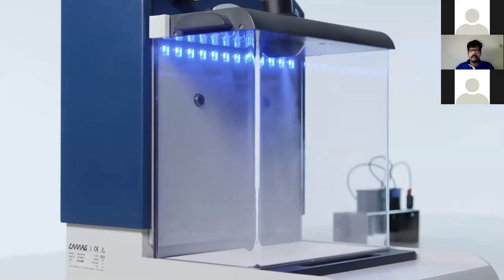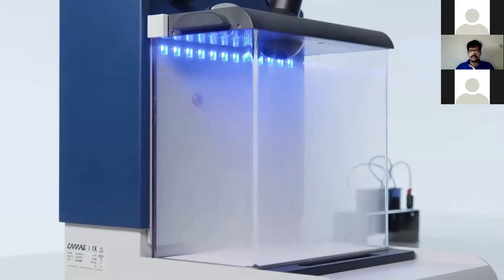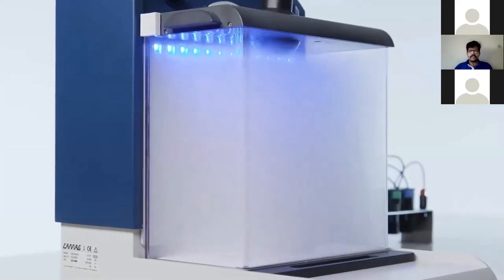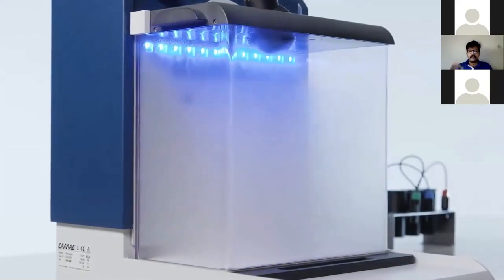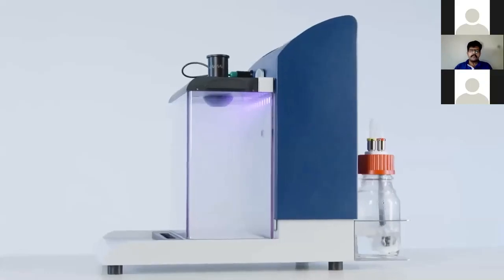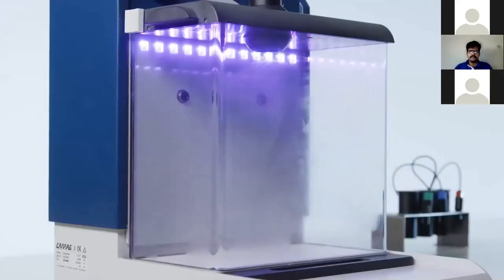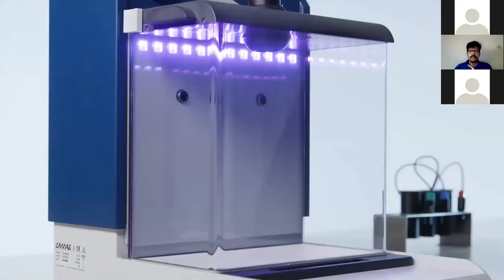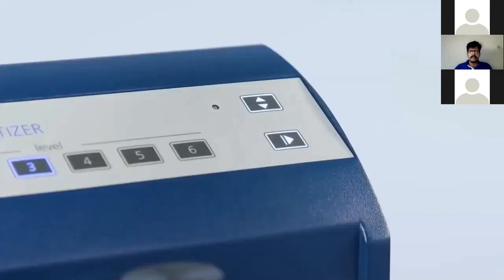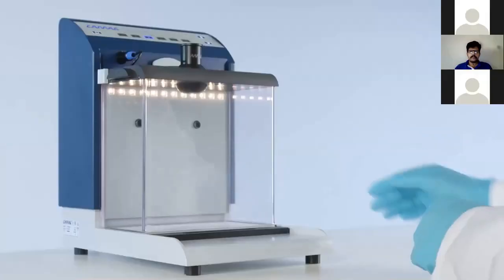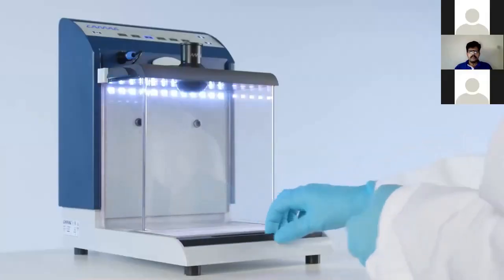And you can see how the nozzle generates an extremely fine mist of this derivatizing reagent, which evenly distributes in the hood and gradually condenses on the plate, and the bands are absolutely sharp and quantifiable even after derivatization. Reagent remaining in the gas phase is automatically aspirated and collected in the wash bottle. When the spraying process is completed, excess fumes are cleared with solvent deposition there in the bottle. Push the button, lift the bottle and lower the hood for further processing.